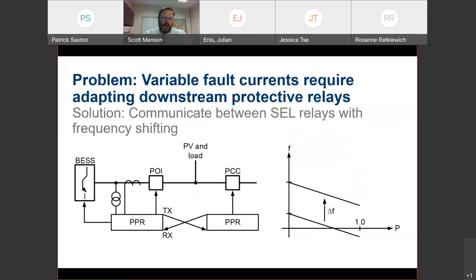Now, here's another example. As you have variable fault currents supplied by batteries and renewables, not only levels, amplitudes, but also characteristics in the time domain, those inverters won't produce many times enough current for protective relays to even pick up and trip. So here's an example. Let's say you have a utility connection and it produces, let's say, 20,000 amps of current. Protective relays are coordinated, let's say on the order of 4,000 or 5,000 amps settings with load around 3,000.